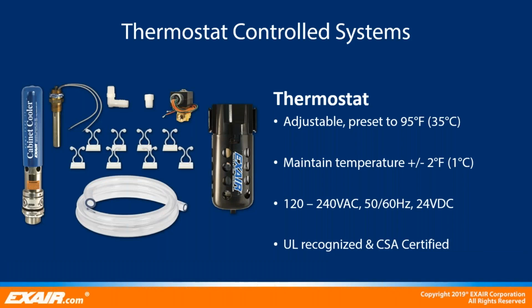Thermostat controlled cabinet cooling systems are the best option when experiencing fluctuating heat loads caused by environmental or seasonal changes. Thermostatically controlled systems include a cabinet cooler, adjustable thermostat, solenoid valve, a cold air distribution kit consisting of tubing, self-adhesive clips to duct the cold air inside the panel, and a filter separator to remove any water and contaminants from the supply. The adjustable thermostat is a bimetal electromechanical switch, factory set for 95 degrees Fahrenheit. We chose this setting because, as we discussed earlier regarding some of the more common devices found in a panel, like VFDs, this meets the recommended set point by the manufacturer. It will normally hold a plus or minus 2 degrees Fahrenheit temperature inside the cabinet.